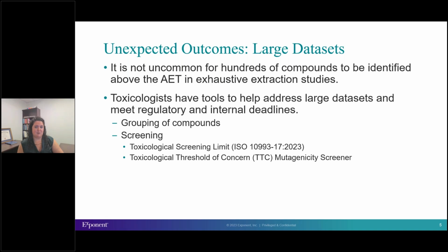So any constituents that are non-genotoxic and below that 90 micrograms per day threshold, we can then justify not requiring a full TRA. However, the success of this approach can be limited by the device material and the expected extractables profile. So we always make sure to consider this before going through this approach, as it can require a bit of effort on the front end.